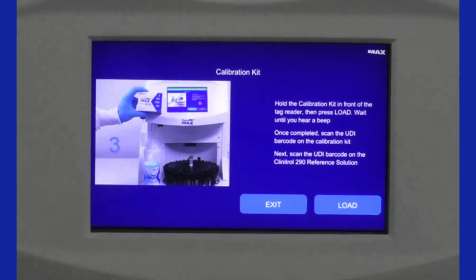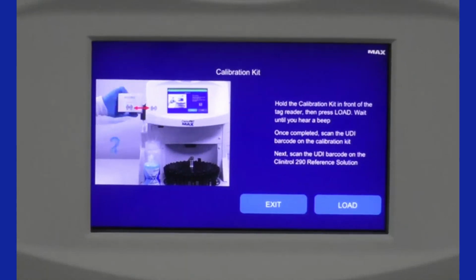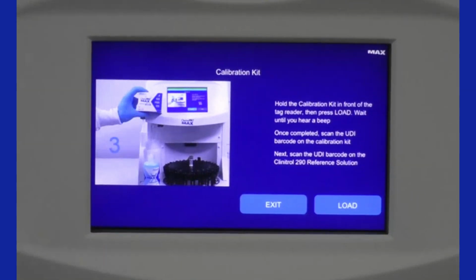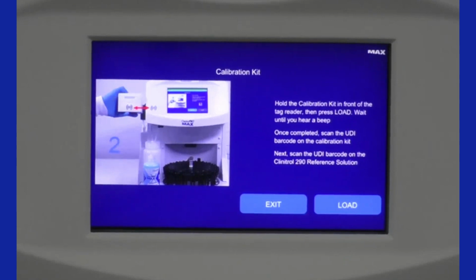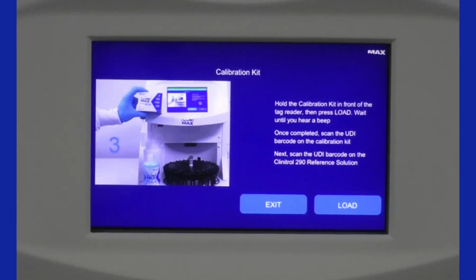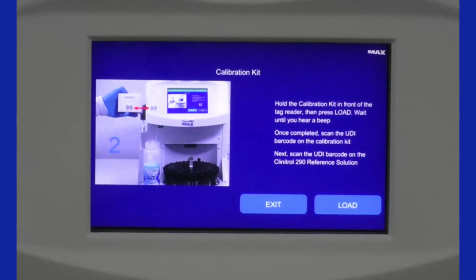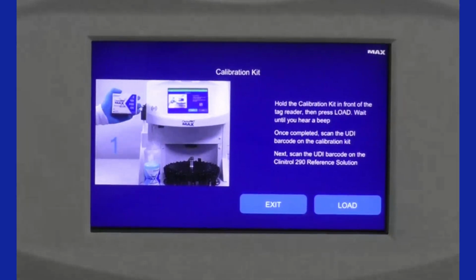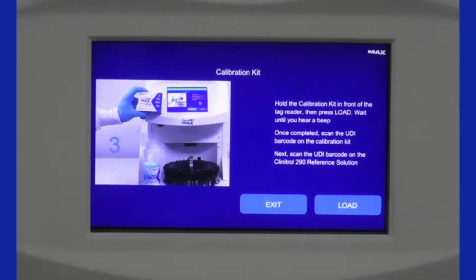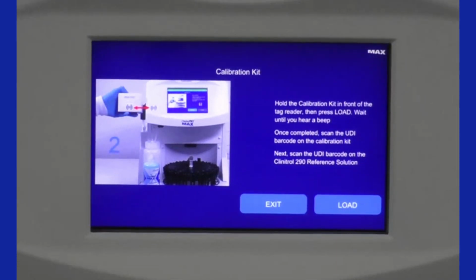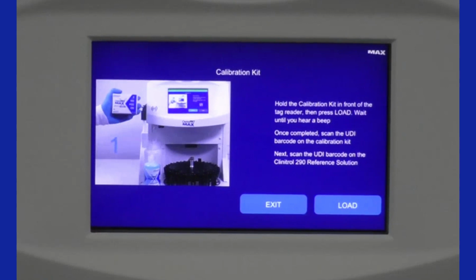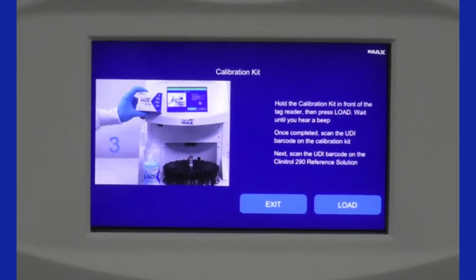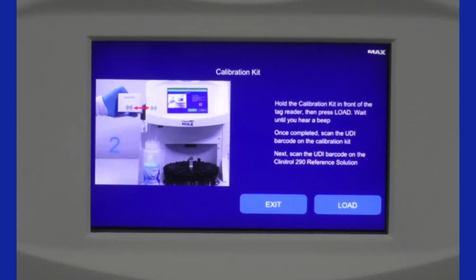So this is what it looks like when you initiate your calibration protocol or your Max 500 kit maintenance protocol. The first thing that's going to pop up is a list of instructions on the right and a step-by-step, frame-by-frame instructional video on the left, showing you exactly what to do. So the first thing it's having you do when you initiate the calibration procedure is scan in your RFID reader for your calibration kit, and then you'll hit load, and all of the instructions that you need to perform that calibration will pop up on the screen, and it will actually show you a step-by-step little video frame by frame of where to load each calibration standard and which calibration ampule and in what position on the 20 sample turntable.